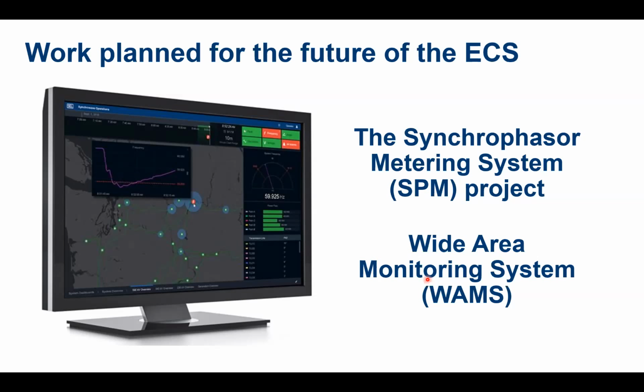What is more, in the substations and power plants where we currently have only PMUs installed, the PMUs we could also use for ECS purposes in the future. If we decide to put the ECS system in these substations where we have only synchrophasor PMUs, we can use the synchrophasor PMUs also for ECS purposes. So this is a kind of integration of two systems. Parts of the synchrophasor systems can be used as ECS relays, and on the other hand, ECS relays are capable of providing synchrophasor measurements.